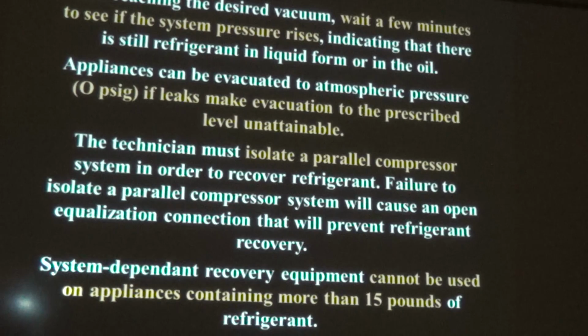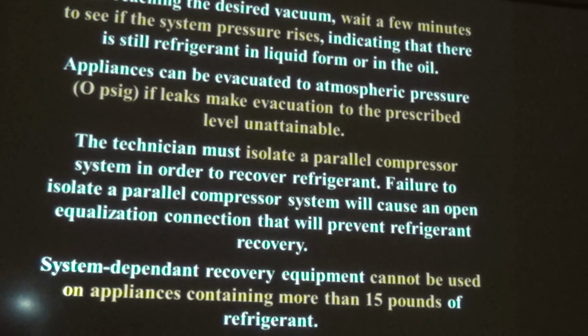If you're working with supermarket refrigeration where they have compressors in parallel, you have to isolate them or you're not going to get to the proper recovery. And you can't use system-dependent recovery if you're using appliances that hold more than 15 pounds. So you just can't use the compressor of the system you're working on if it holds 15 pounds. You have to use an external recovery machine that has its own compressor.